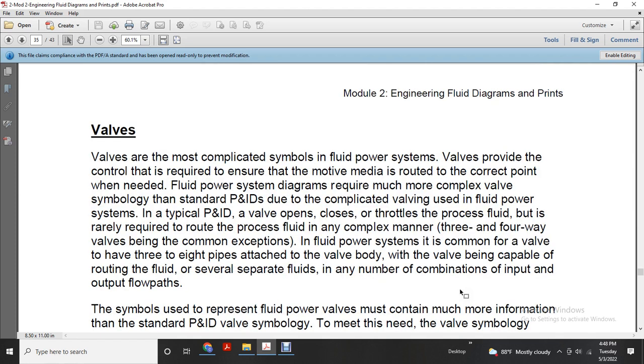Valves are the most common symbols of the fluid power system and the most complicated of the symbols. Valves provide the control required to ensure the media is routed to the correct point when needed. Fluid power system diagrams require much more complex valve symbols than piping and instrument drawings, due to the complicated valves used in fluid power systems. In piping and instrument drawings the valve opens or closes the process fluids, but rarely is any complex valve required for the process fluid, while a 3 or 4 way valve is a common exception in fluid power systems.